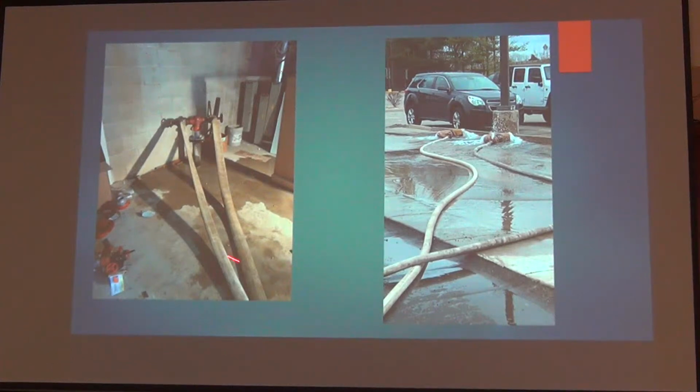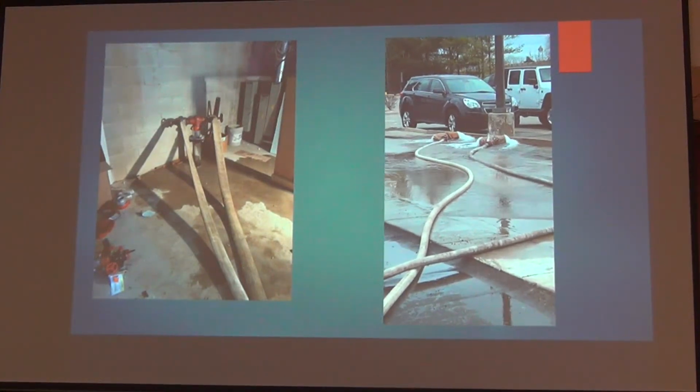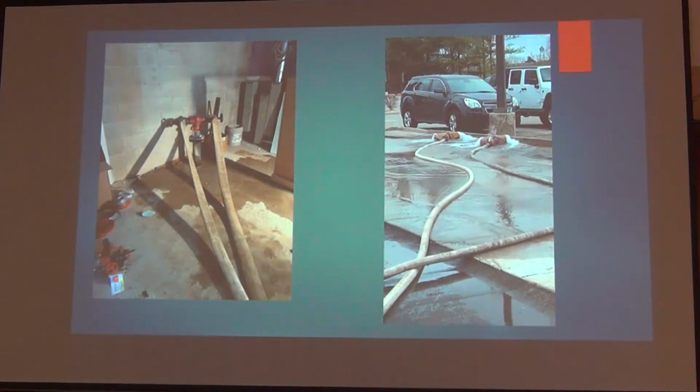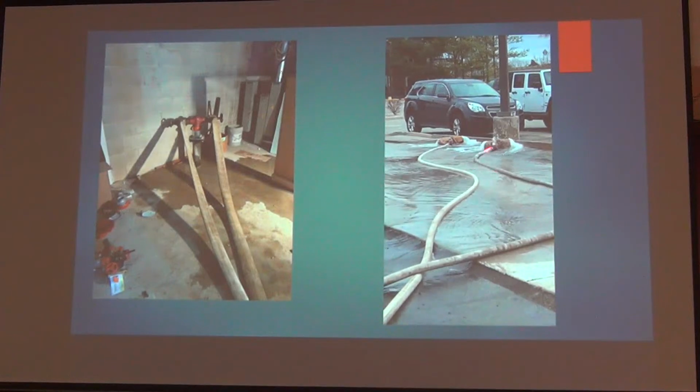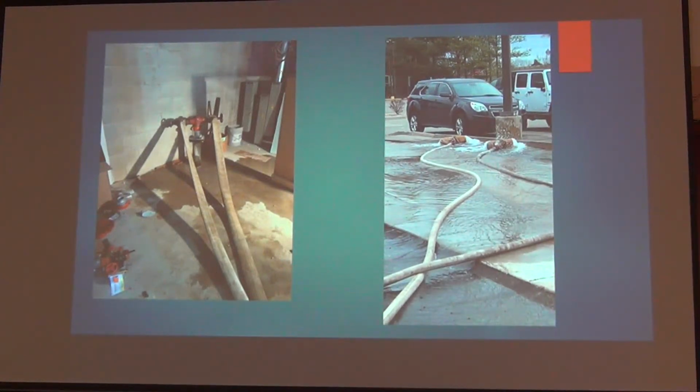Okay, they hook up the hoses, they run it out, they put a hose monster on there with a burlap bag so they can catch all the debris so we know what's in there. And then they flow water. You'll see this mud coming in this direction. Once the water clears there, you start timing 5 minutes at that flow.